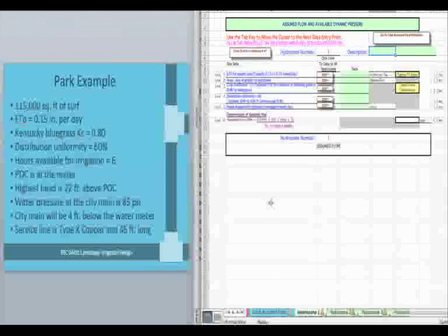But to begin with, we're going to use this hydrozone 1 sheet and we're going to fill in as much information as we can. Line 1 asks for the reference ET for the project site, and it tells you that that's typically between 0.15 and 0.35 inches per day.